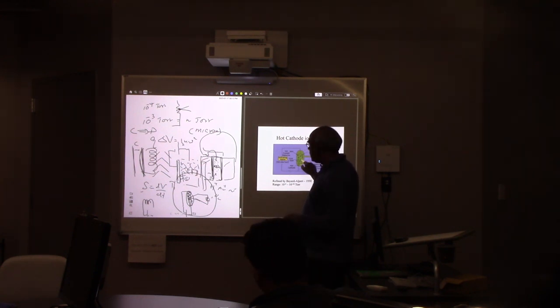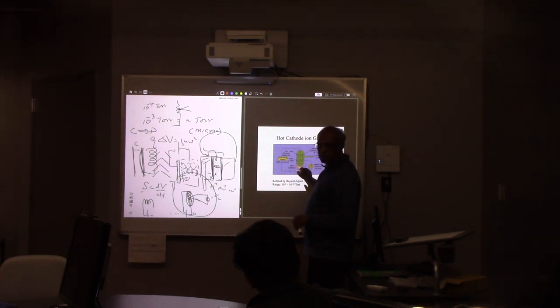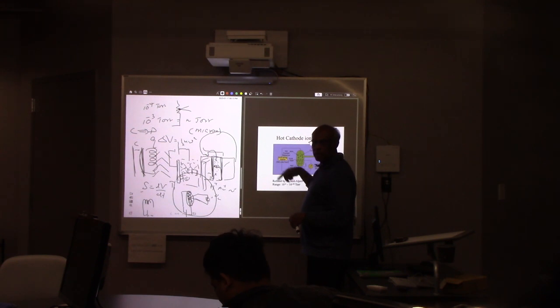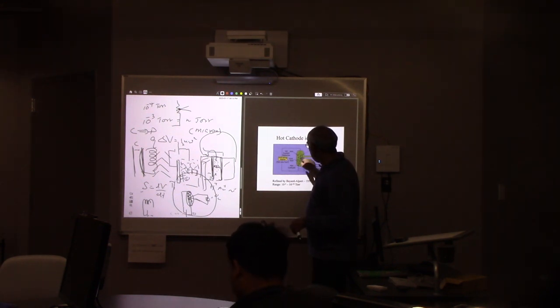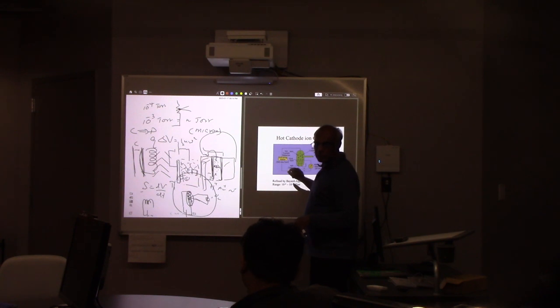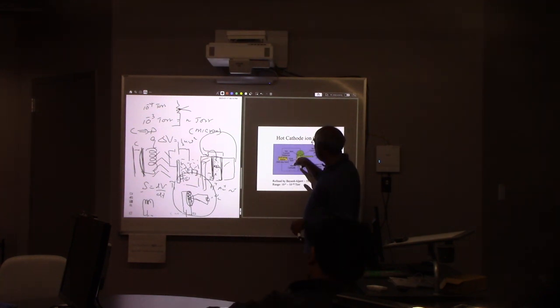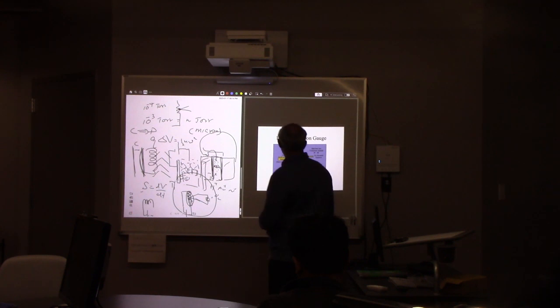If you pump the system, then you have a smaller number of ionized charges. What will happen to this current? That will be less, right? Because if you have more, then you have larger current. If you have fewer ionized charges, you have less current. So that means the current is directly proportional to that vacuum. That's basically how the ion gauge works.